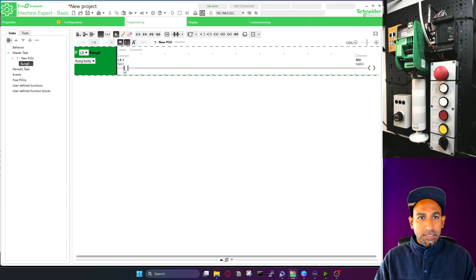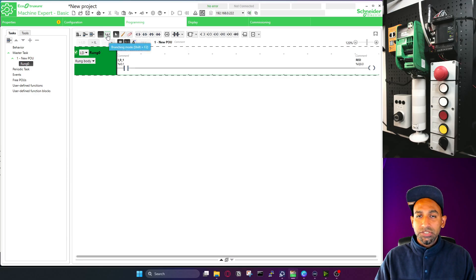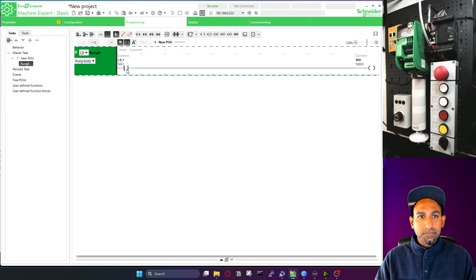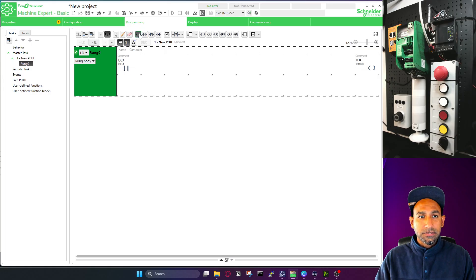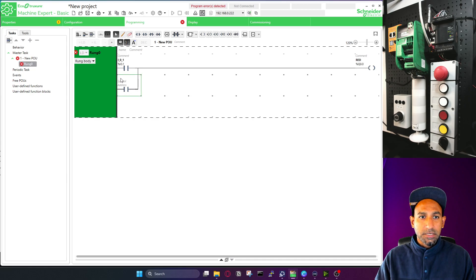This is my NO contact, and you know how this program works — I will turn this on and it will turn on my output. But what if I want to add something in parallel? There is an option here — by default it's normal mode, no branch. Switch to branching mode, bring your mouse here, take the contact you want to branch next to it, and click. Now it is in parallel.